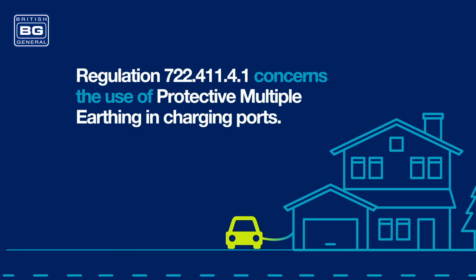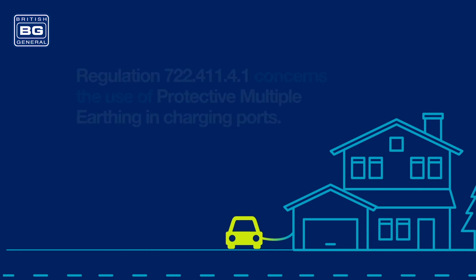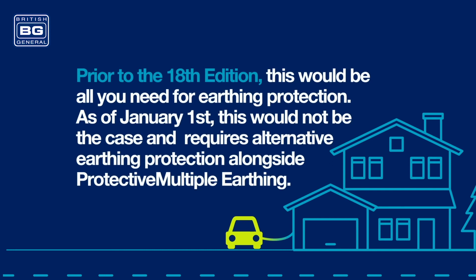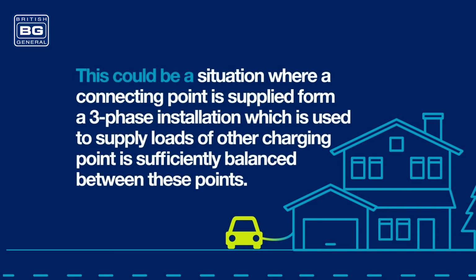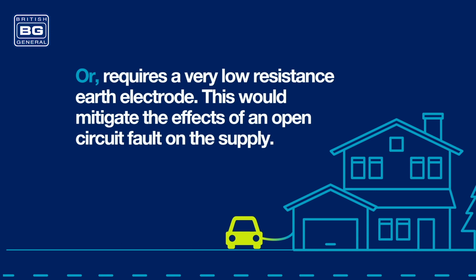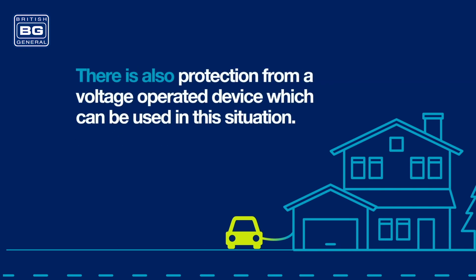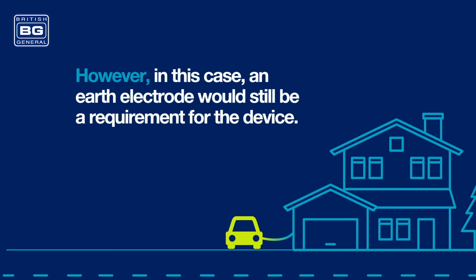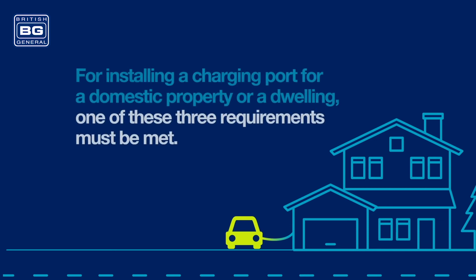Regulation 722.411.4.1 concerns the use of protective multiple earthing in charging ports. Prior to the 18th edition, this would be all you need for earthing protection. As of January the 1st, this would not be the case and would require alternative earthing protection alongside protective multiple earthing. This could be a situation where a connecting point is supplied from a three-phase installation which is used to supply loads of other charging points sufficiently balanced between these points, or requires a very low-resistance earth electrode. This would mitigate the effects of an open circuit fault on the supply. There is also protection from a voltage-operated device which can be used in this situation. However, in this case, an earth electrode would still be a requirement for the device. For installing a charging port for a domestic property or a dwelling, one of these three requirements must be met.